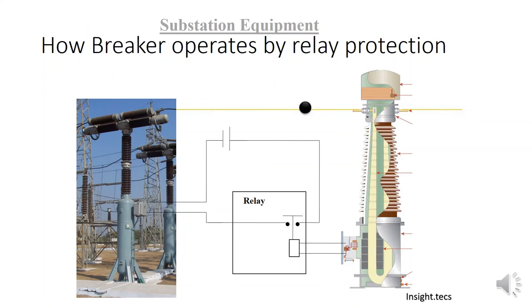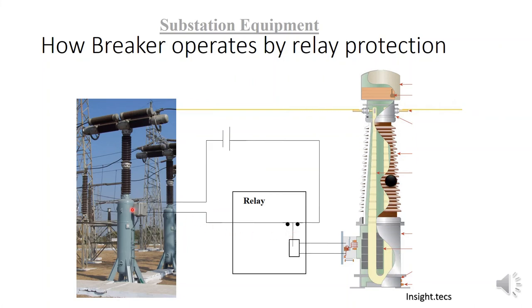Whenever a fault occurs, a high amount of current flows through the CT, which results in more current in its secondary terminals. Due to this, the relay gets energized, the circuit closes, and the trip command is given to the circuit breaker. Due to the current flowing, the relay operates and the trip command is sent to the circuit breaker, so the breaker gets tripped.